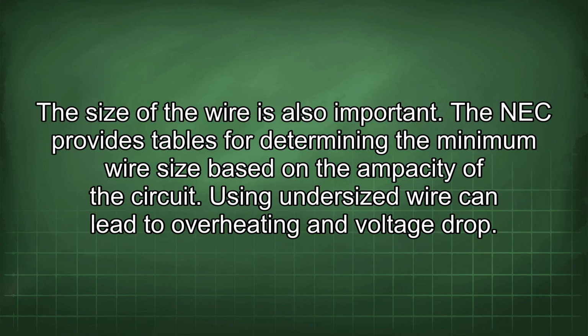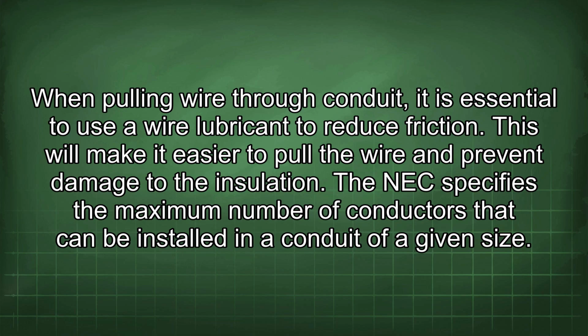The size of the wire is also important. The NEC provides tables for determining the minimum wire size based on the ampacity of the circuit. Using undersized wire can lead to overheating and voltage drop. When pulling wire through conduit, it is essential to use a wire lubricant to reduce friction. This will make it easier to pull the wire and prevent damage to the insulation.